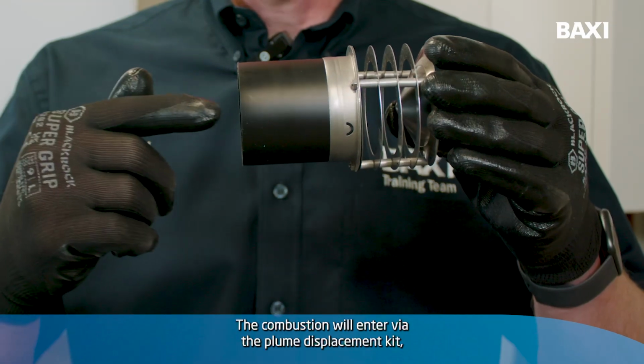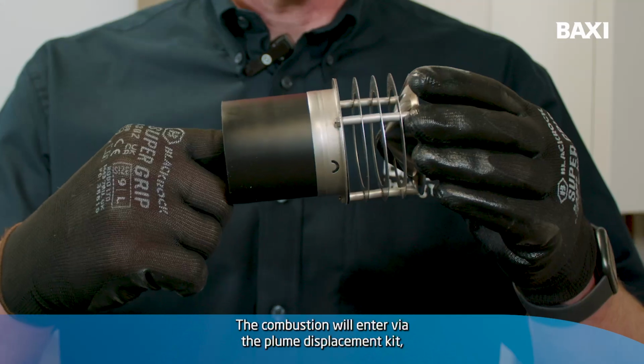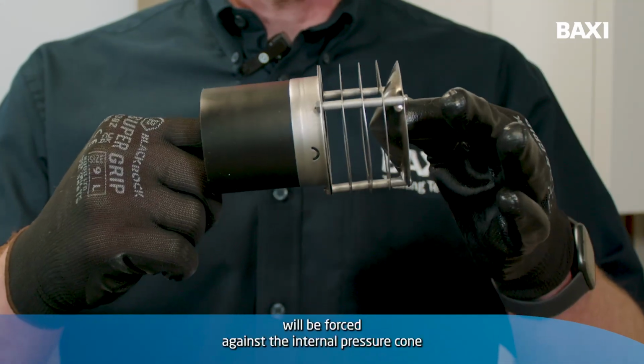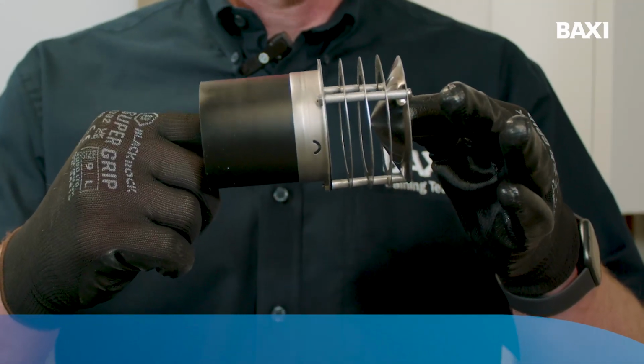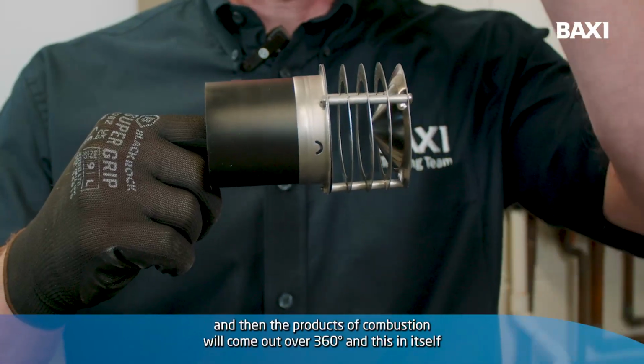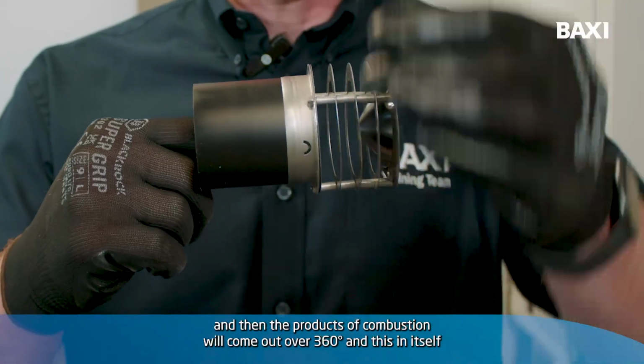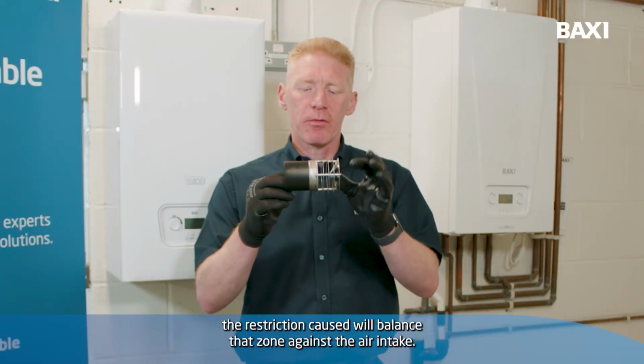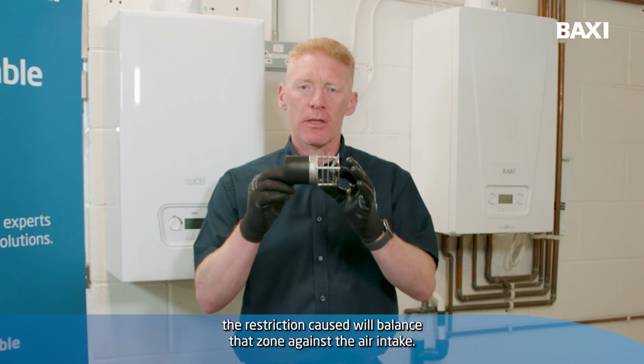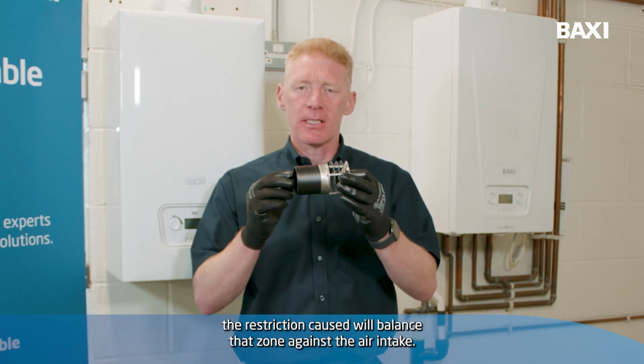The combustion will enter via the plume displacement kit. It will be forced against the internal pressure cone, and then the products of combustion will come out over 360 degrees. And this in itself, the restriction caused, will balance that zone against the air intake.